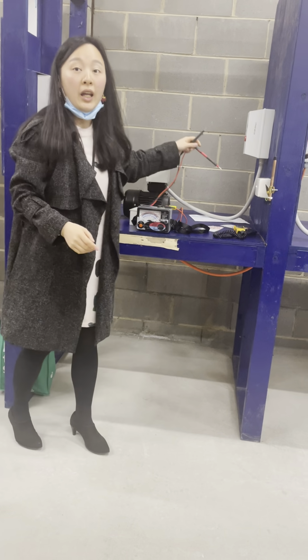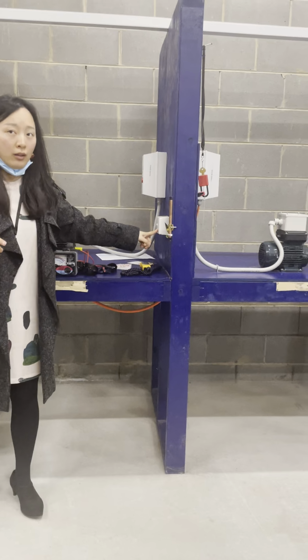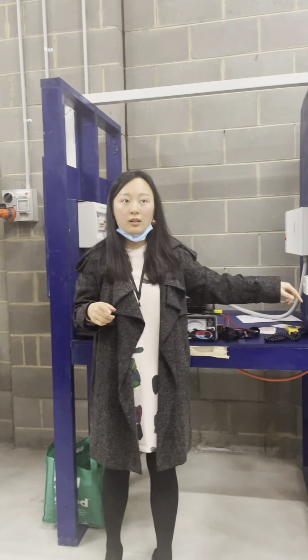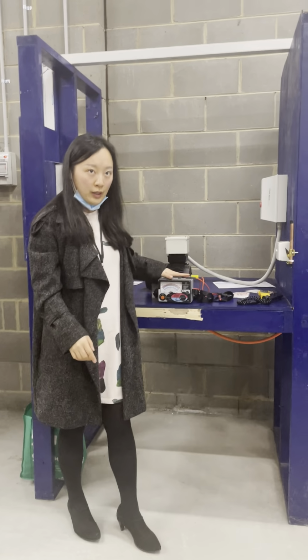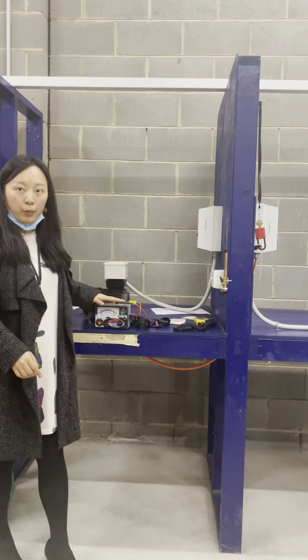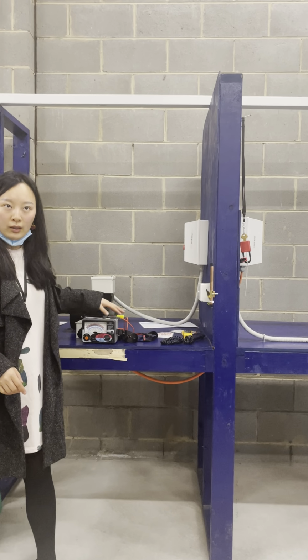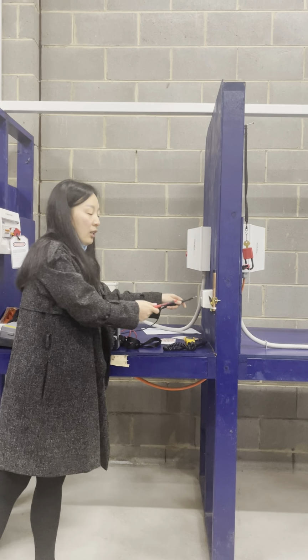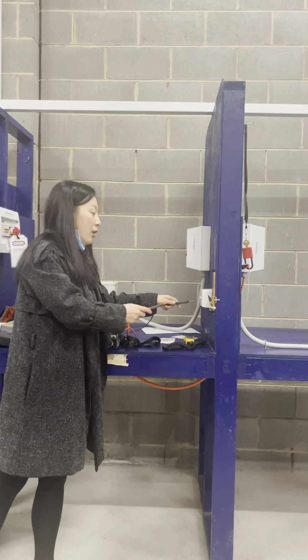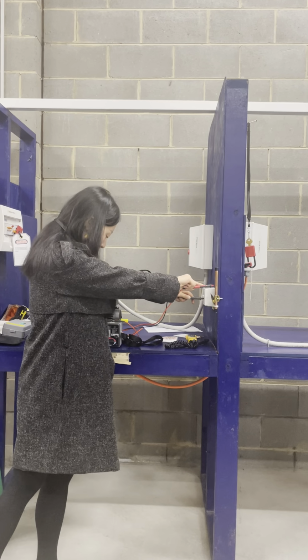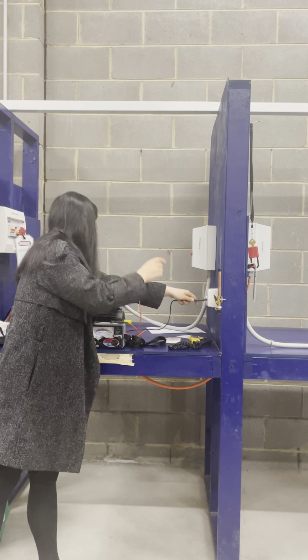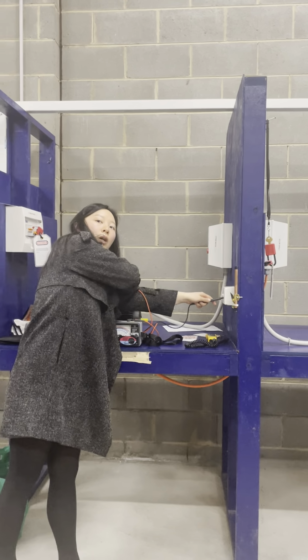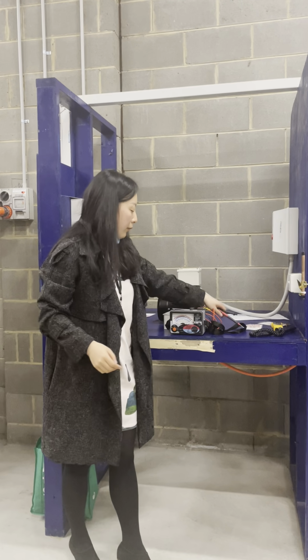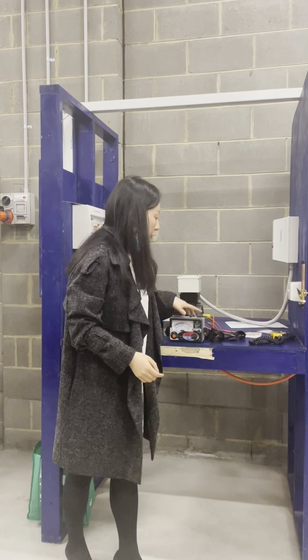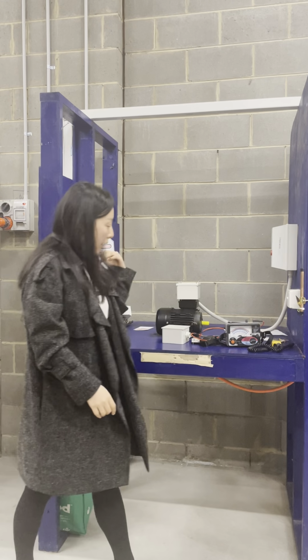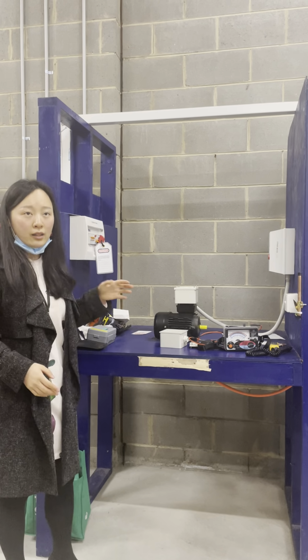That's good. If you've got to the GPO earth and the effective earth as the first step, you're supposed to do this before the 3 point. Is it clear? So if you've got to do this as the first step when you do the reconnection, you can do it now. So check this earth continuity first, 0 ohms, and then check for 3 point, 1, 2, 3. Okay, retest your tester. Good. We confirm the earth system is all good. Now I can go to the switchboard, and make sure you ask for approval again.